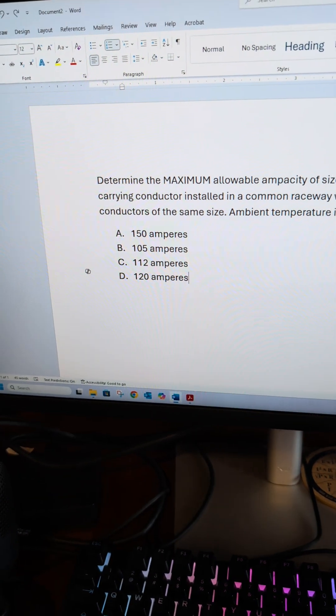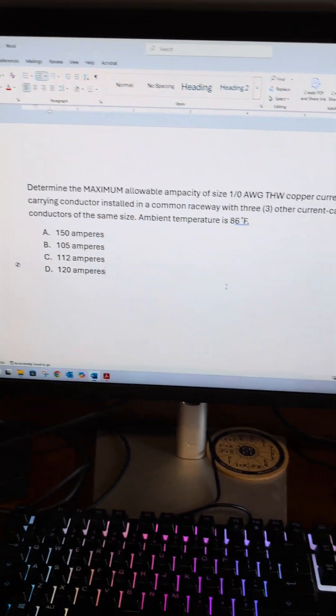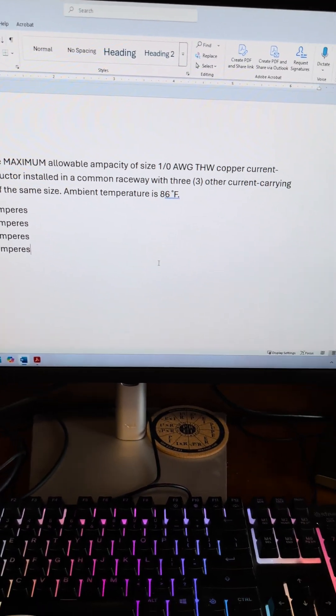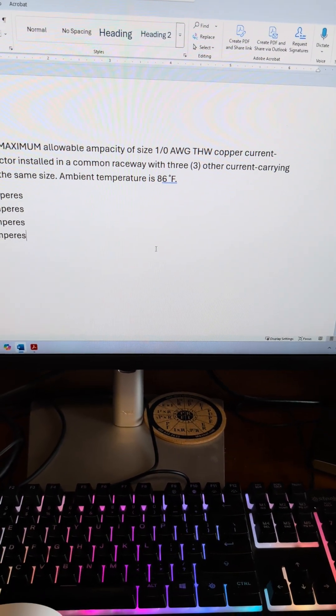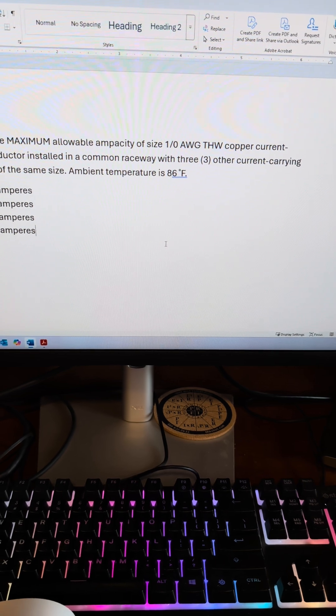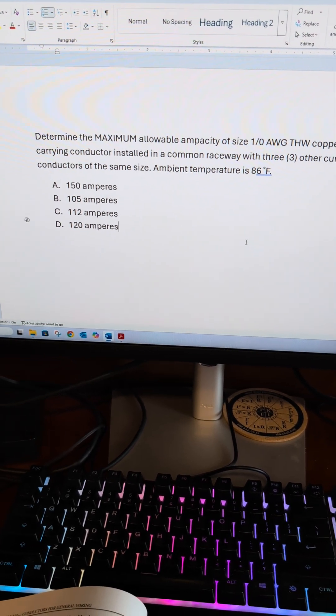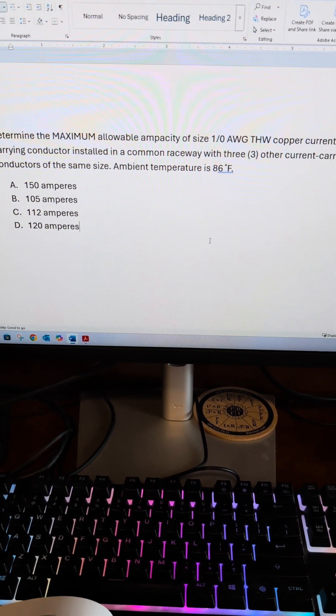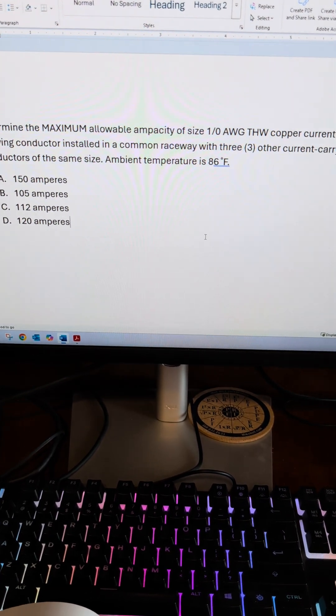Now even though 150 amps is an answer choice, there's two other things in this question: three other current carrying conductors and an ambient temperature of 86 degrees Fahrenheit. We're going to need to correct and adjust.